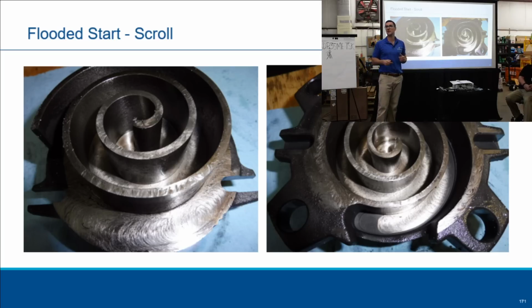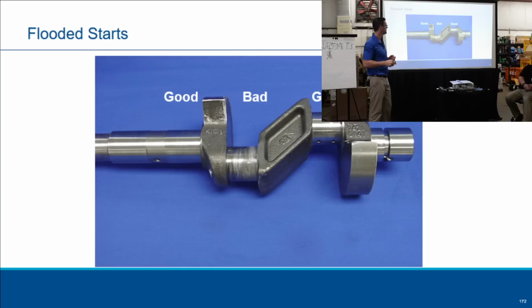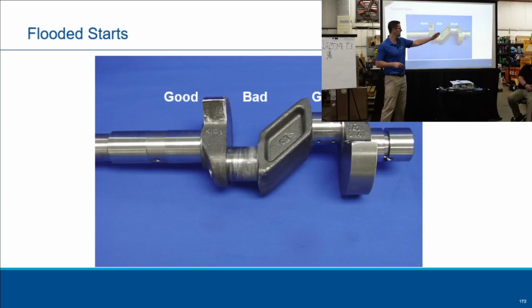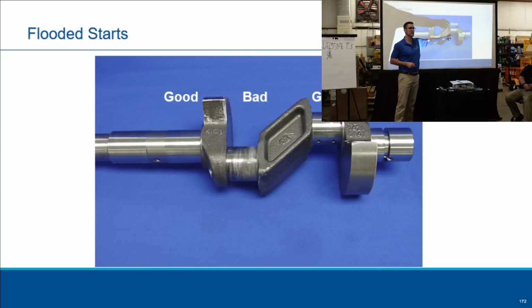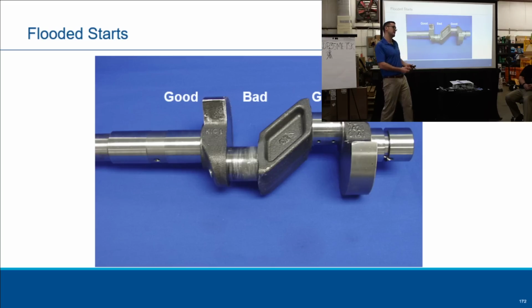And then you're in a heap of trouble now. Okay? On semi-hermetics, a good, bad, good scenario. So progressive wear and flood back, but you can see here, this is the third one, right? You could see it sometimes when you're trying to get an oil pump off and the oil pump's stuck and you're trying to pull it off and you're banging and you get a screwdriver in there, a big one, or a pry bar, and you pop it off if you can.